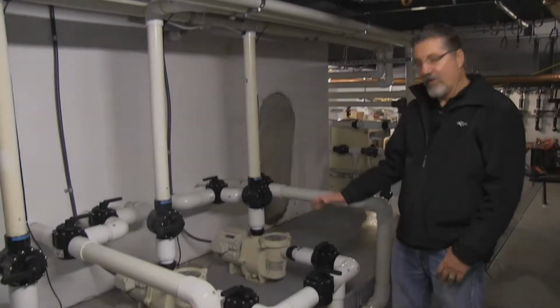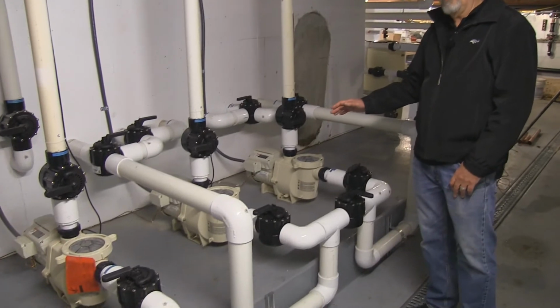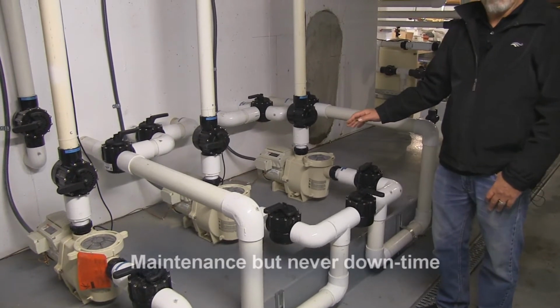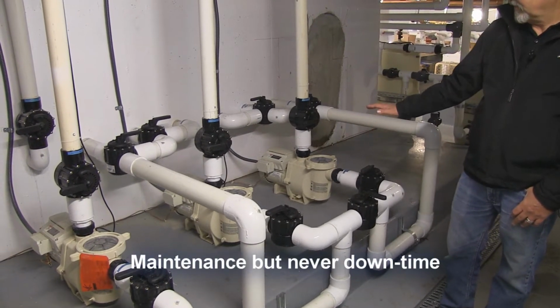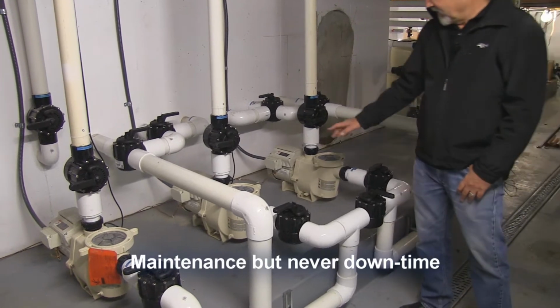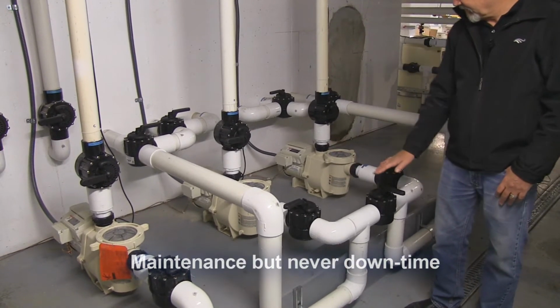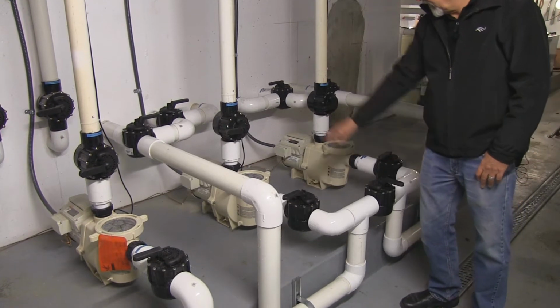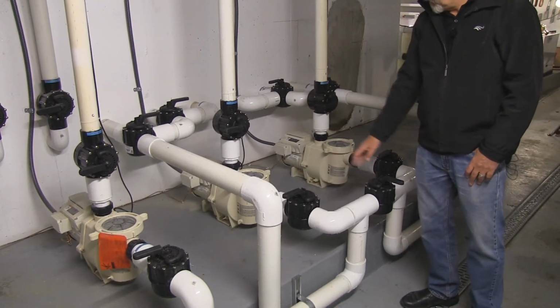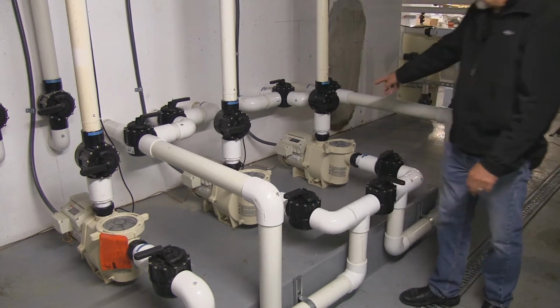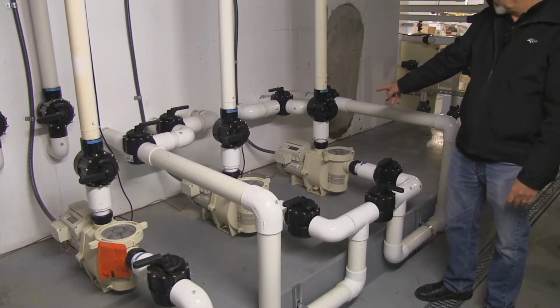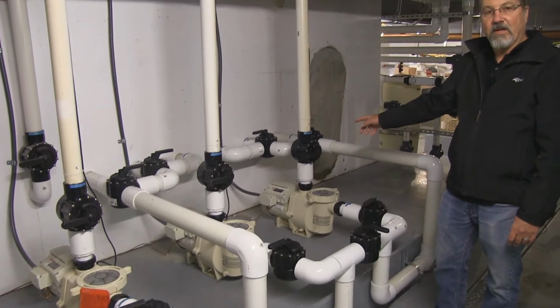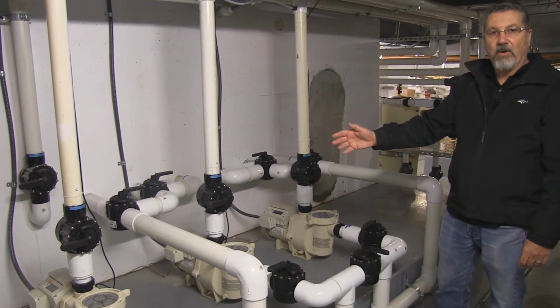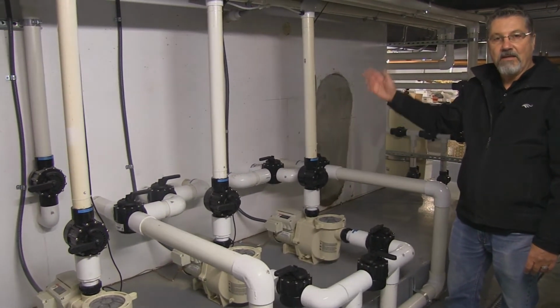During the design, it was important for us to make sure that if a pump needed service or maintenance or had to be pulled for anything, you could run the system on one pump only. So regardless of where we're drawing from, skimmers or main drains, if one pump is down, we can isolate that valve and open this up, now drawing from both sides of the pool. We can ramp up this pump, since it's a variable frequency drive pump, and circulate the entire system through one or the other pump, filter, and maintain heat and a safe swimming environment.